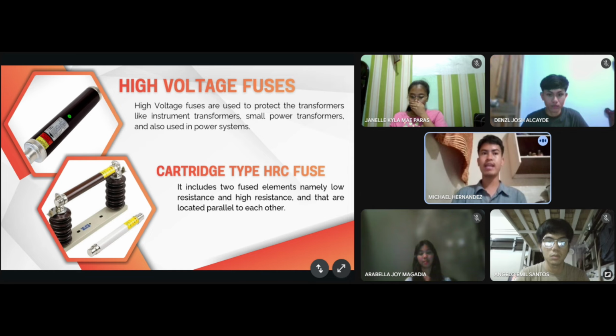The fuse looks like a simple sealed tube, but inside it is carefully engineered. It contains a fuse element made of silver or copper and is filled with a special powder, often quartz sand, that helps extinguish the arc formed when the fuse blows.